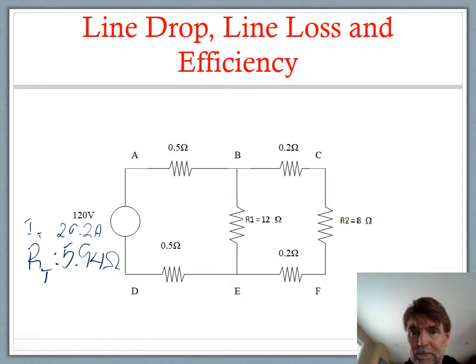This also means there are 26.2 amps there and 26.2 amps down here. Although typically I just do the work on one wire, not both—they're going to be the same numbers. Where do we go next? We can calculate the voltage drop on that wire.